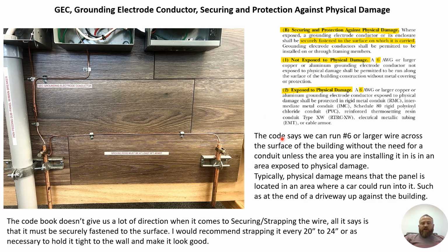So in that scenario, if you were installing it at the end of a driveway, you would have to install it in some type of conduit, preferably PVC, so that you don't have to bond it on both ends like we learned in the last slide.